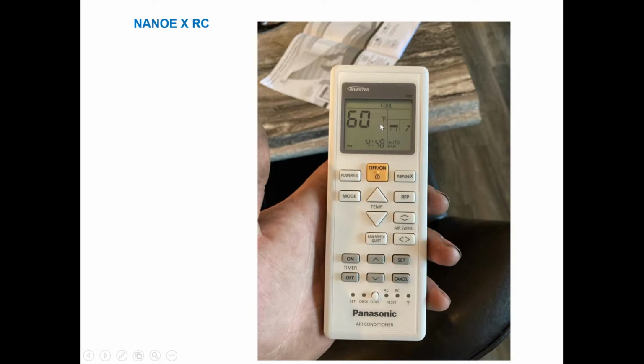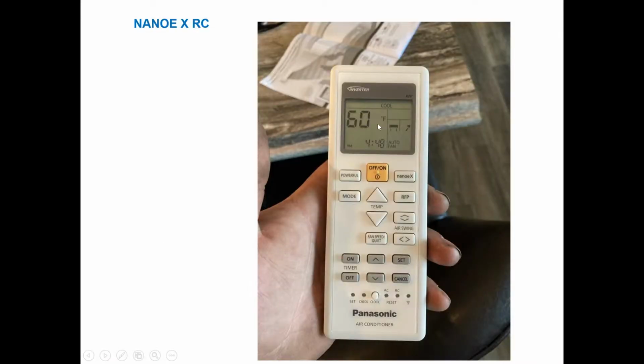The screen changes. You get two dashes with the timer up and down. Not the temperature, guys, but the timer up and down. Scroll until you hear the beep. When you hear the beep on the indoor unit, stop. When you stop, you look at the remote controller and it will say H11 or H99 or whatever. Okay, so simple. You can save a lot of time. You can save a lot of hours.